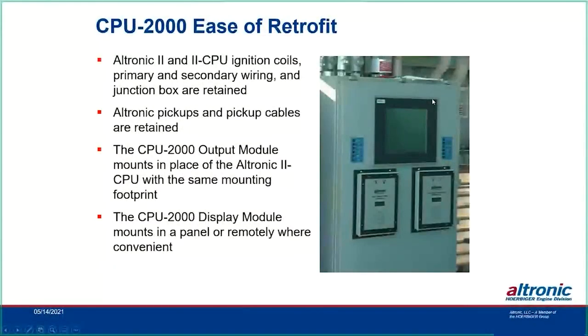Ease of retrofit from Altronic 2 to CPU-2000: the existing coils are retained — Altronic 2 coils can be expensive, and a 16-cylinder dual-plug engine may have 32 coils. The CPU-2 and CPU-2000 all utilize the same coils, so all you need to purchase is the CPU-2000 display module, output module, and appropriate cables, then add ring gear and reset pickups and harnesses. That transitions you from an Altronic 2 to full CPU-2000 current technology.